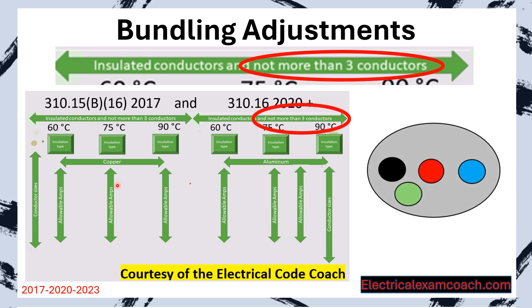Let's imagine that we have a piece of conduit and we pulled in a black, red, blue, and an equipment grounding conductor. What this table is saying is that those ampacity values are true as long as you have not more than three current carrying conductors in a cable, pipe, or raceway. If you do have more than that, then we have to do what's called a bundling adjustment.